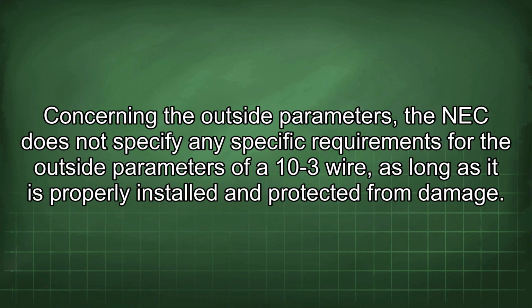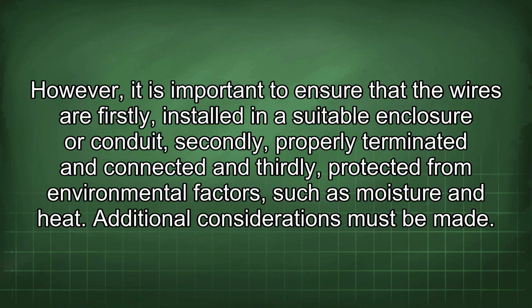Concerning the outside parameters, the NEC does not specify any specific requirements for the outside parameters of a 10-3 wire, as long as it is properly installed and protected from damage. However, it is important to ensure that the wires are, firstly, installed in a suitable enclosure or conduit, secondly, properly terminated and connected, and thirdly, protected from environmental factors such as moisture and heat.